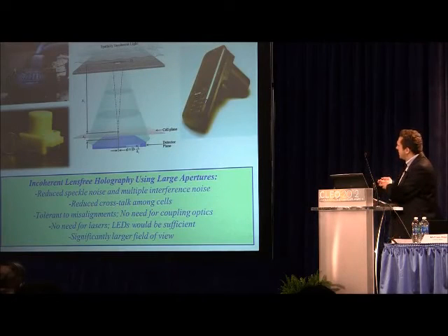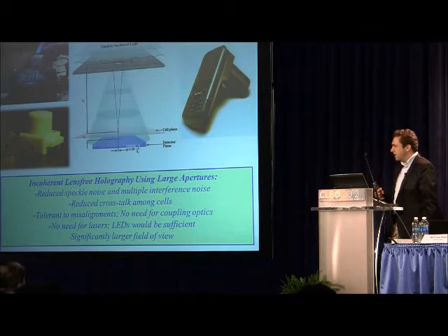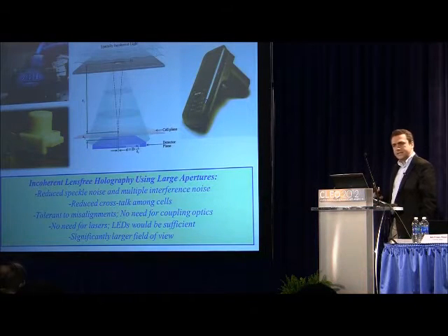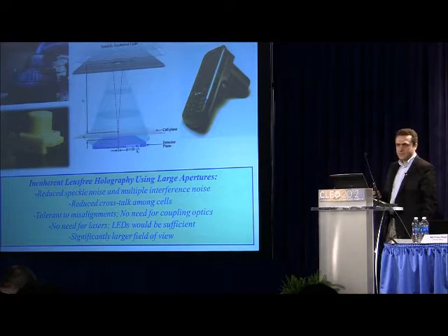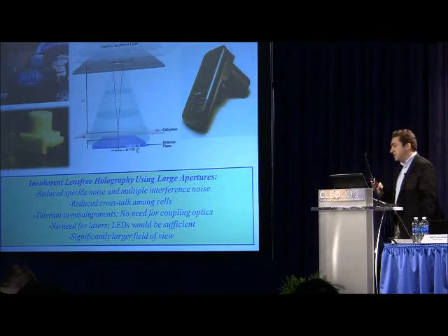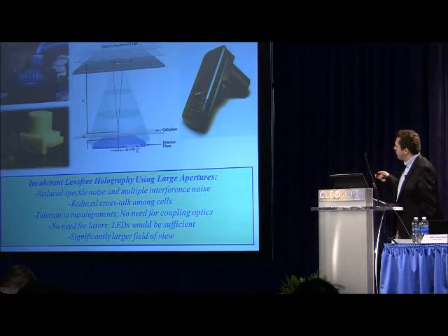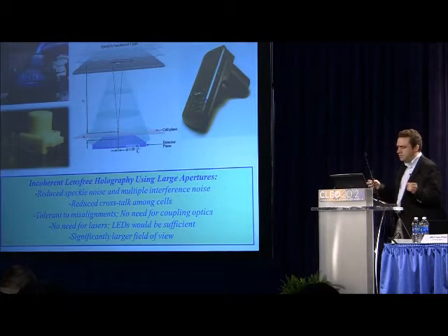So whether it's running on a cell phone or a standalone unit or a benchtop system as shown here, these microscopes, these microanalysis tools, are working based on partially coherent illumination. It's holographic in the sense that we are recording fringes that convert the phase information of the specimen into intensity oscillations. However, the source is not a laser, it's actually a light emitting diode. It could be sunlight as well. What we do is we play with the geometry of this microscope so that we have partial coherence that's sufficient to record holograms of individual cells.